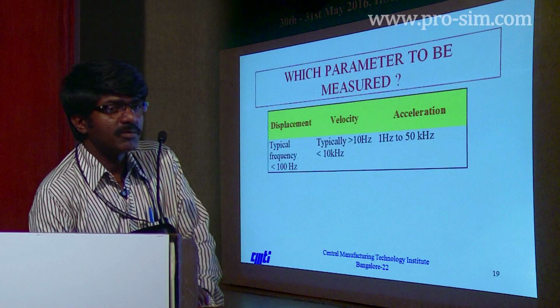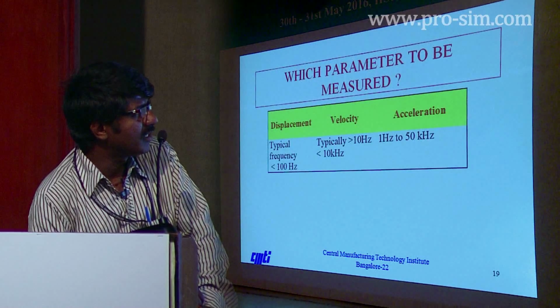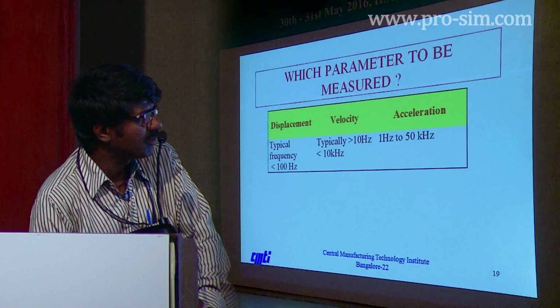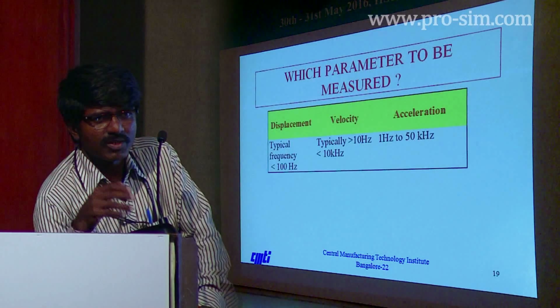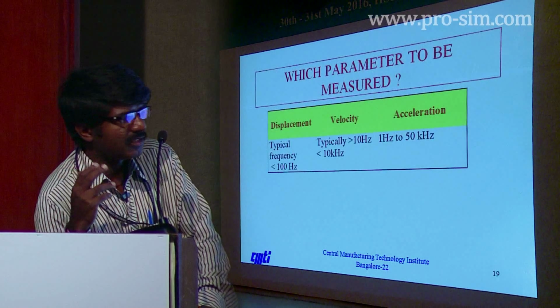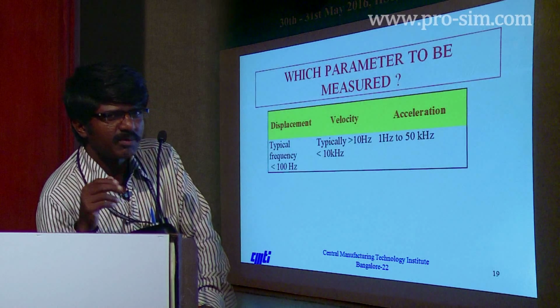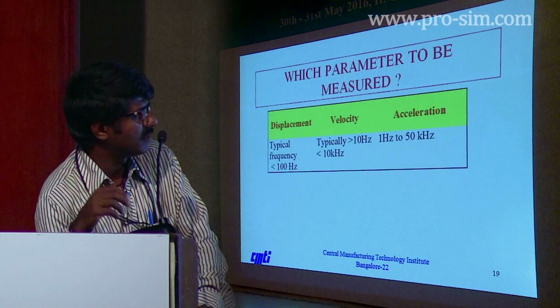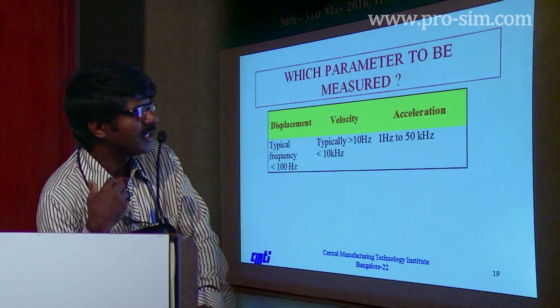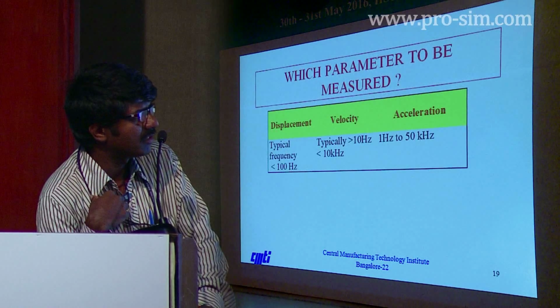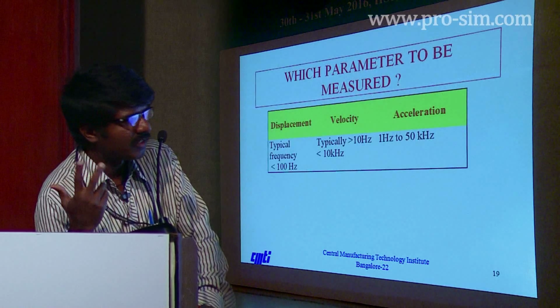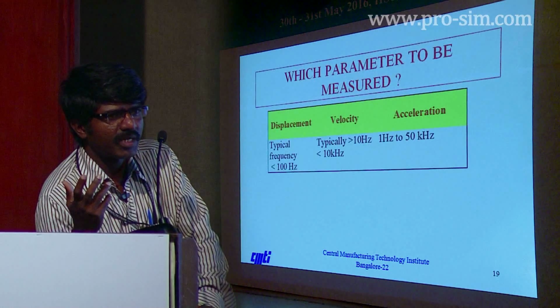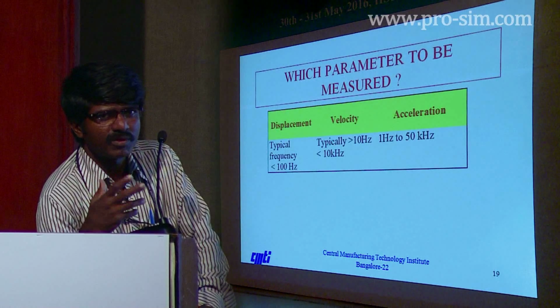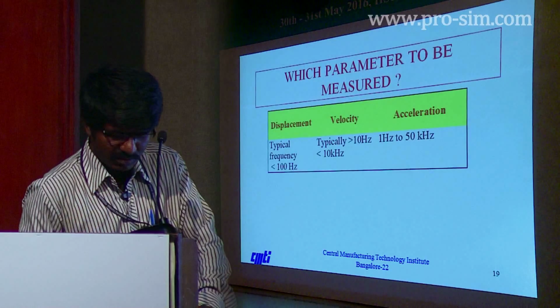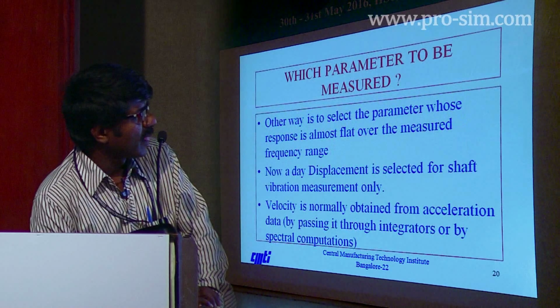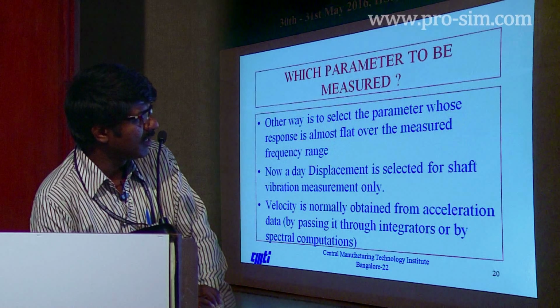Okay. So next comes which parameter we have to use for predictive maintenance. Suppose we are doing a vibration monitoring. You know very well that you can measure vibration in terms of acceleration, velocity and displacement. Displacement is recommended for frequencies less than 100 Hz. Velocity we can use from 10 Hz to 10 kilohertz. Acceleration we can use from 1 Hz to 50 kHz. Only thing is that we have to select a parameter which gives flat response over a wide frequency range. That is a must. So that's what is described here.